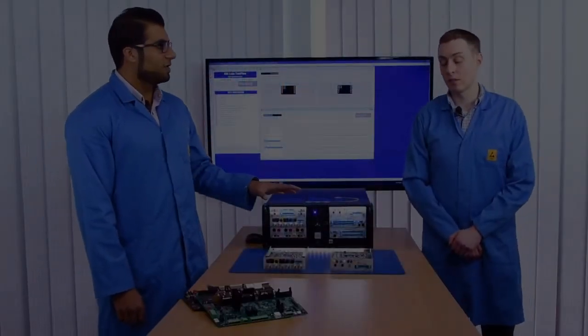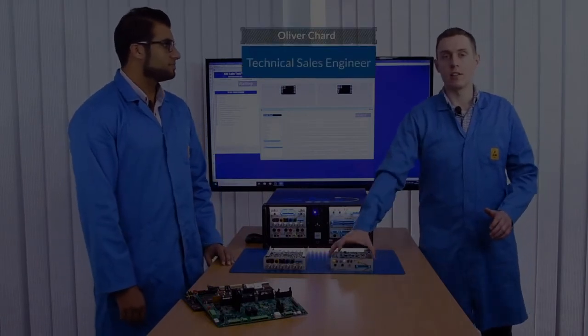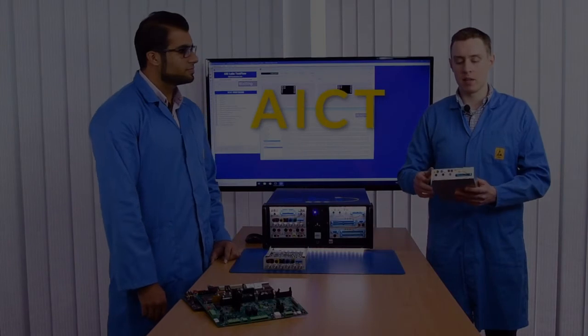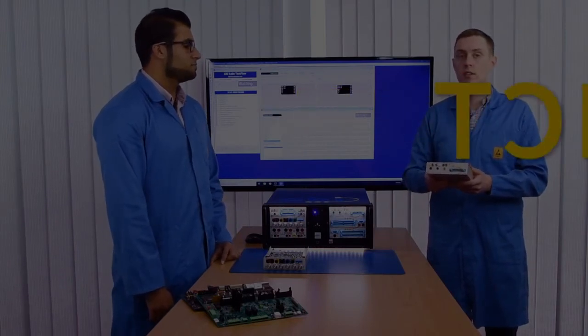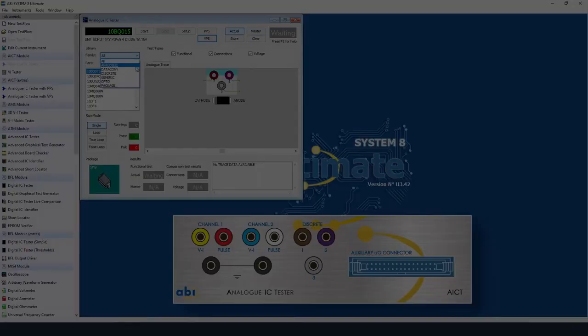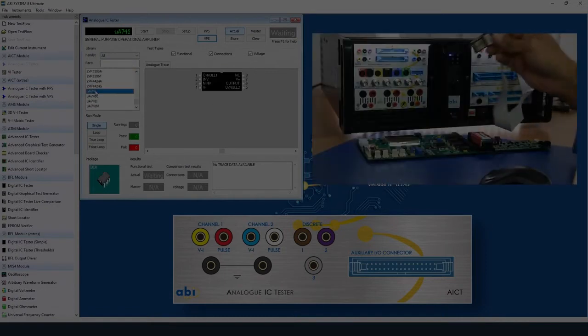So Oliver, what can you tell us about the analog IC tester? The analog IC tester which we've abbreviated to AICT is our module for testing analog devices both power on and power off. It comes with a library of analog devices from comparators, operational amplifiers, op-amps and optocouplers and it also can measure discrete components as well.